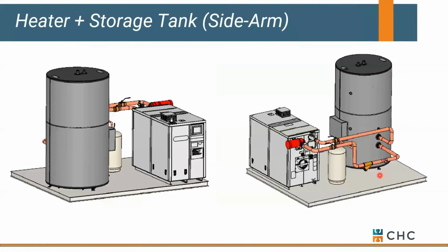Okay. We see a lot of engineers, and I'm not picking on engineers, owners and contractors. We get a lot of calls when somebody sees a dedicated appliance heating a storage tank. They tend to call this a boiler. And we've seen engineers say, hey, if this thing gets over 400,000 BTUs an hour, we're going to call it a boiler, even if we're heating domestic water with it. My caution is this creates a lot of confusion. Not only if you install a boiler here and it needs to be a water heater, the inspector's not going to buy off on it. We might have a crane pick to remove it and replace it, and there might be a lot of shuffling going on in the field. Okay, to me, any appliance that is heating domestic water, in this case a domestic hot water storage tank, should be called a water heater.